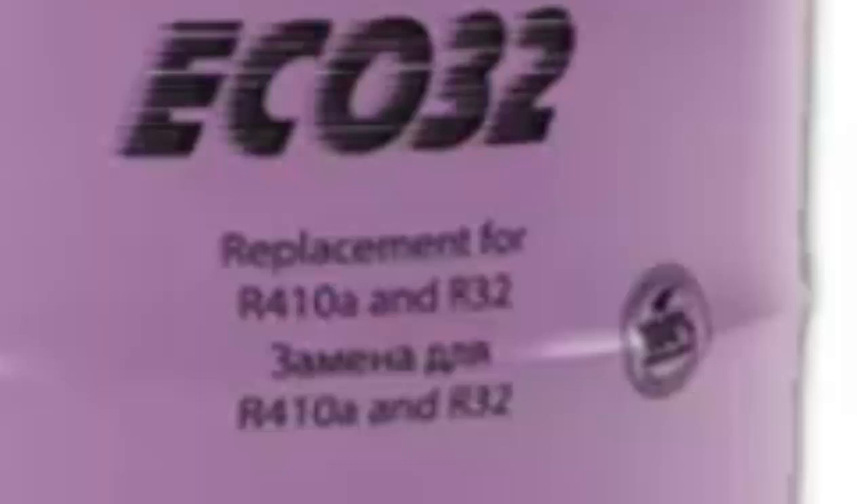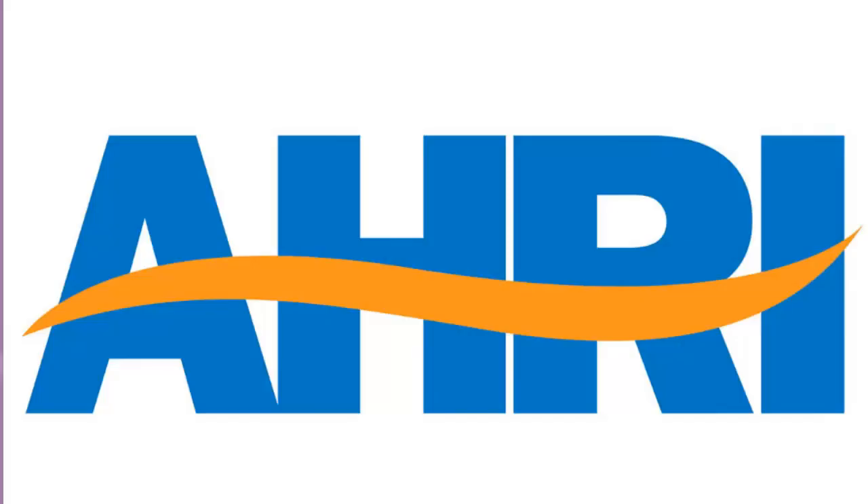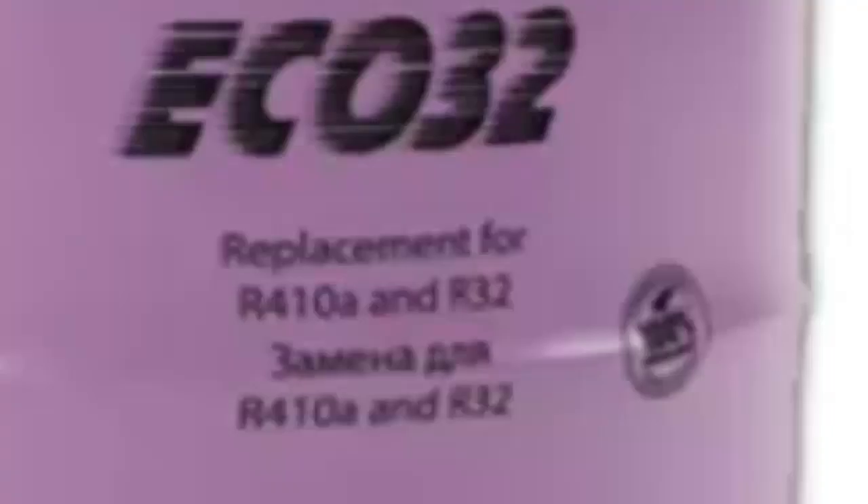However, although R32 is slightly flammable, the flammability of hydrocarbon blends like ECO32 should be considered, as its flammability may be higher than that of R32. According to AHRI, it's important to remember that it's not recommended to replace gases with different degrees of flammability without the manufacturer's authorization.